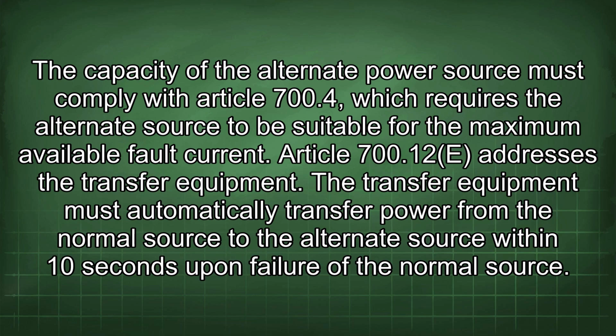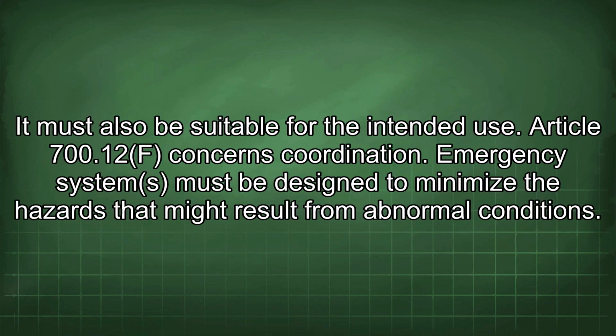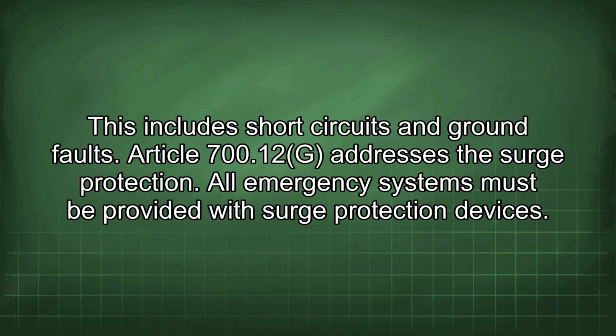Article 700.12(E) addresses the transfer equipment. The transfer equipment must automatically transfer power from the normal source to the alternate source within 10 seconds upon failure of the normal source. It must also be suitable for the intended use. Article 700.12f concerns coordination. Emergency systems must be designed to minimize the hazards that might result from abnormal conditions. This includes short circuits and ground faults.